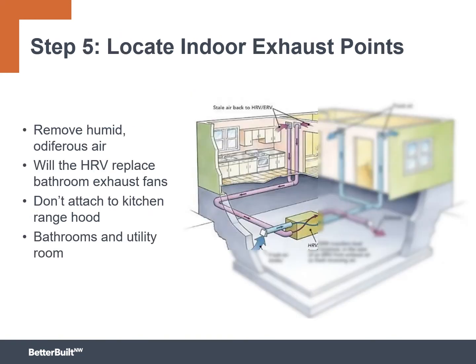Next up, step 5, we want to locate all of our interior exhaust points. So where are we going to pull air out of the house? This is pretty great, because obviously we want to remove pollutants in the places that they're caused. So we want to remove humid and odoriferous air, meaning stinky, smelly air, out of the house. The HRV may be able to displace some of the bathroom fans again. We do not recommend combining this with your kitchen range hood. We really want you to focus on bathrooms and utility rooms.